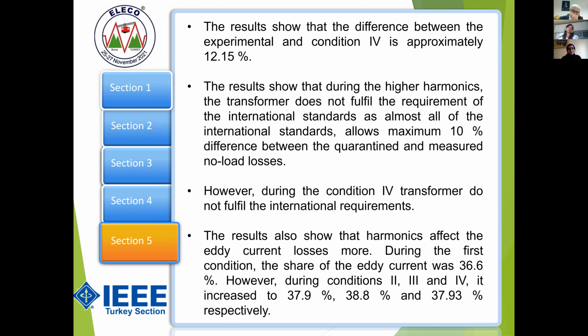In the results, I can conclude that the harmonics affect more the eddy current losses. During the first condition, the share of the eddy current losses was just 36.6%. In the other condition, you can see that it increased to almost 38%. In the third condition, it was 38.8%.